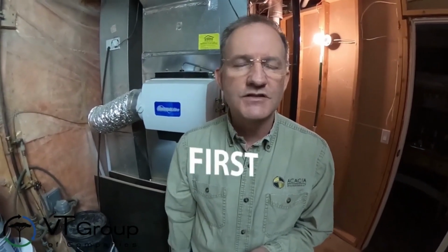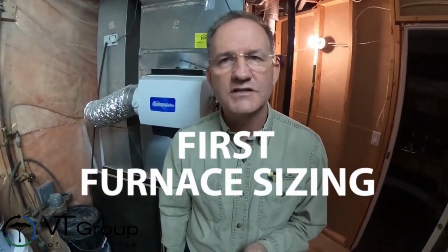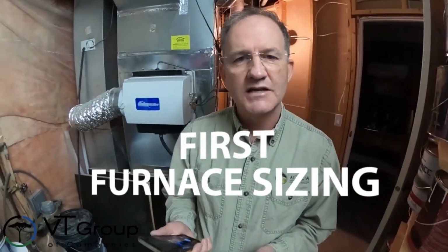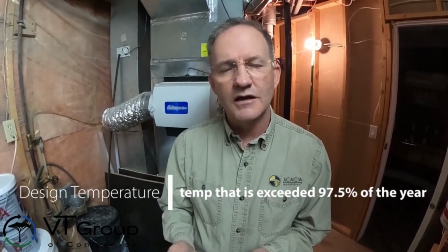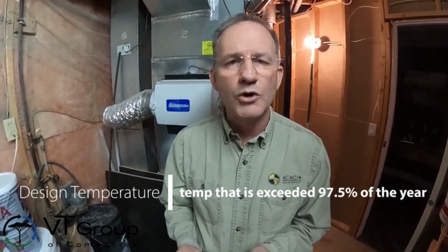One of the very first things to start with is what we call furnace sizing. When we talk about furnace sizing, we're asking how much energy is lost from the house when it's minus 30 degrees outside, which is typically the design temperature for Calgary. Maybe it's minus 32 in Edmonton. There's a special number used from the building code called the design outdoor temperature. It's not the coldest day of the year, it's the temperature we would mostly see 97.5% of the time.